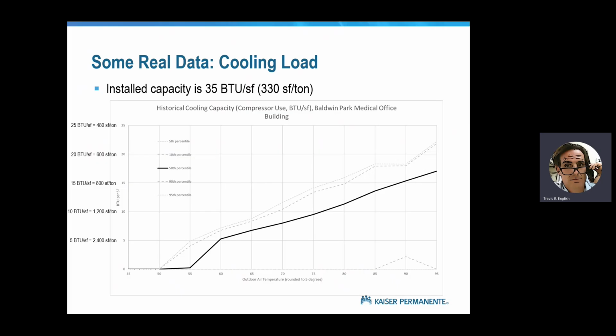This is 1 year of historical data for cooling in one of our clinical buildings. Now, the unit thing is a problem. I grew up as a square foot per ton person. One of my engineers grew up using BTU per square foot, so we find ourselves always converting back and forth. So in this case, the installed capacity was 35 BTU per square foot, which is 330 square foot per ton.